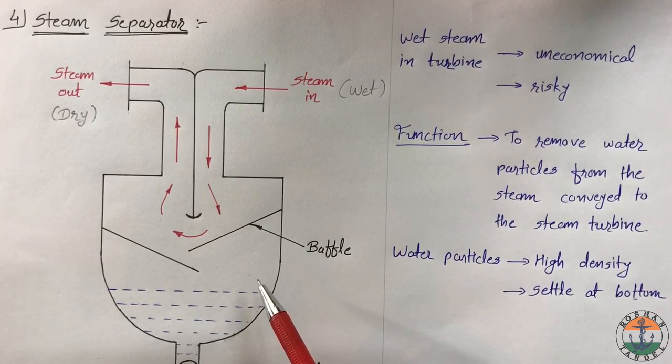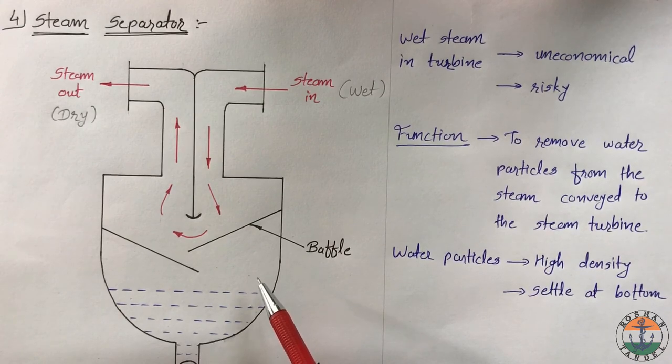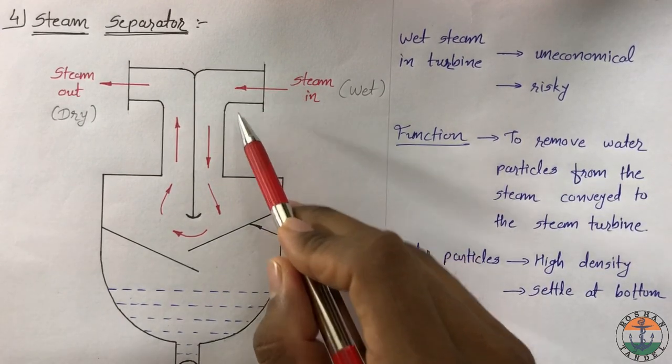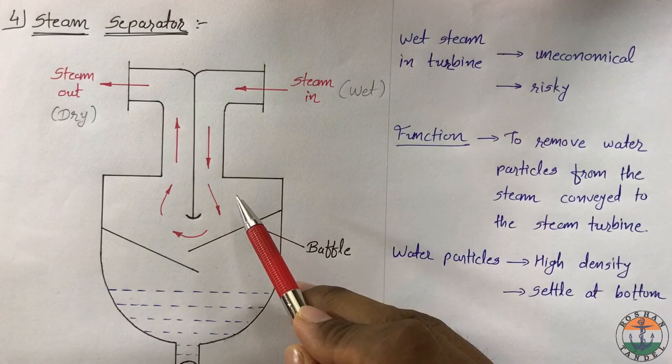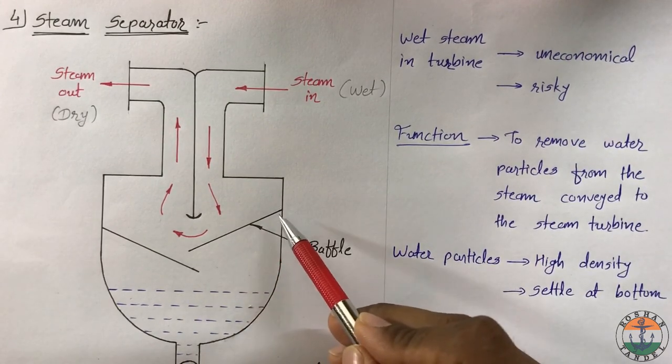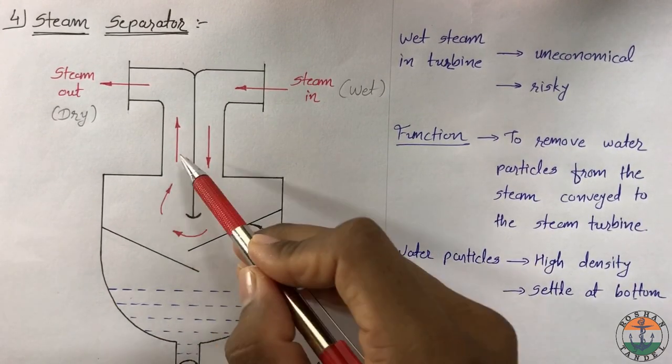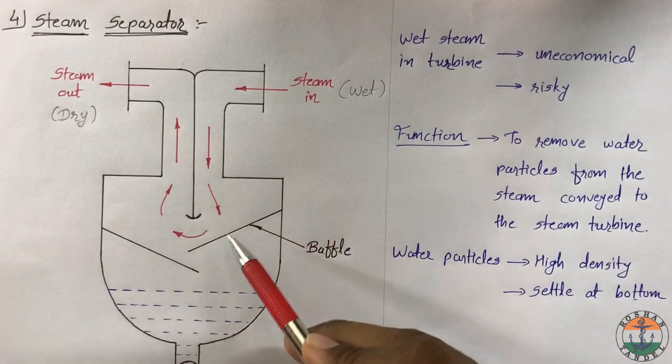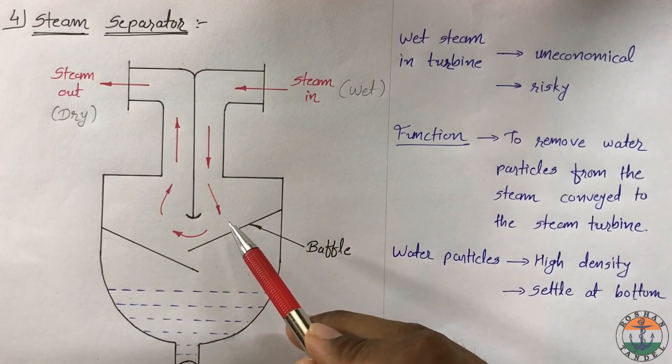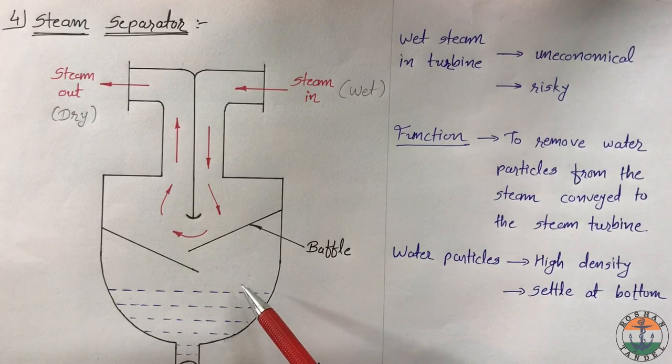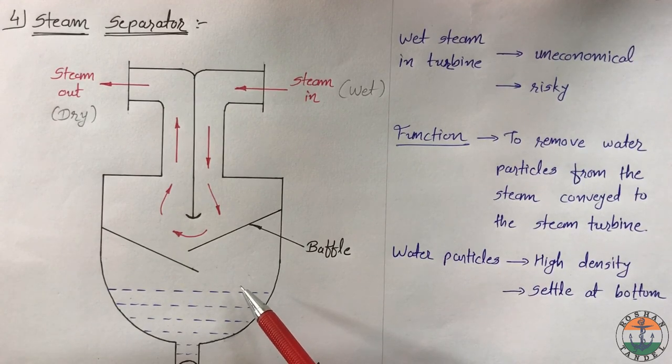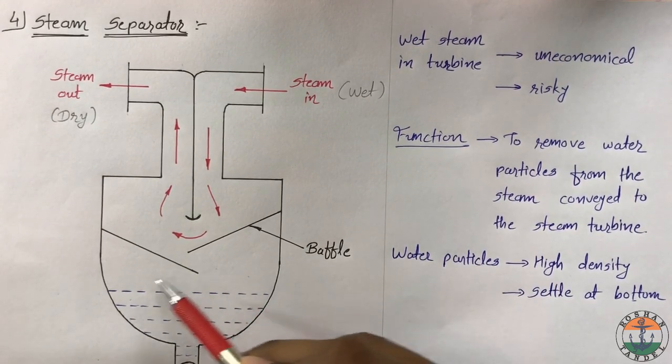Baffle type steam separator is shown here. Steam is passed from one side in the chamber, in which it strikes baffle plates and gets deflected. Because of higher density and inertia, water particles present in the steam fall down at the bottom of steam separator.